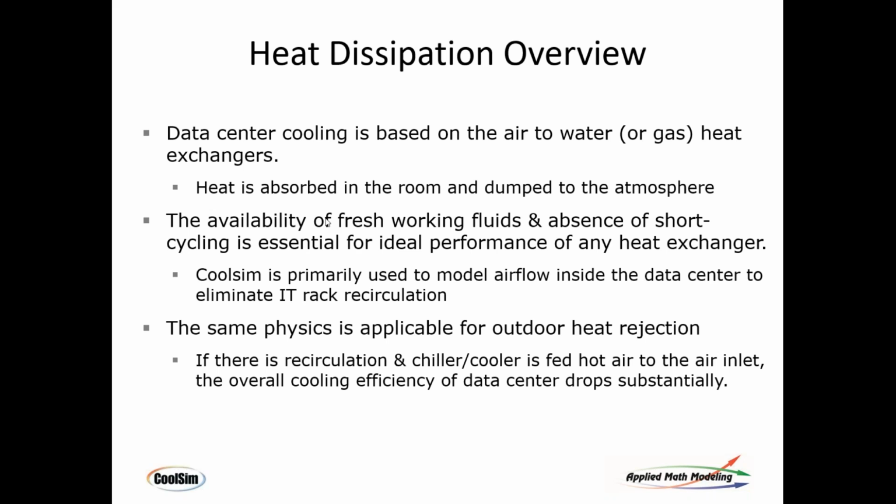And that's primarily CoolSim's job. Inside, we work in the white space, but the same physics is available and applicable on the outside. So outside, you're trying to do the same thing. And oftentimes there is recirculation that happens in the dry coolers or cooling towers or whatever they're trying to use to dump the heat to the outside atmosphere. This causes the efficiency of the data center to drop substantially.